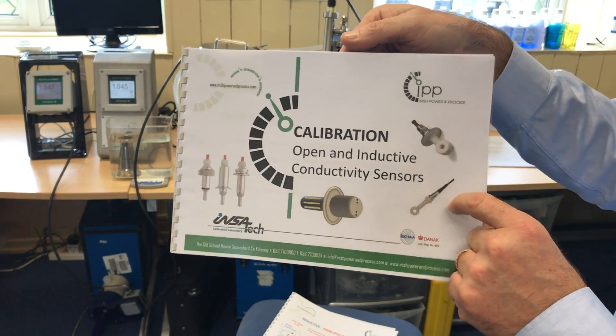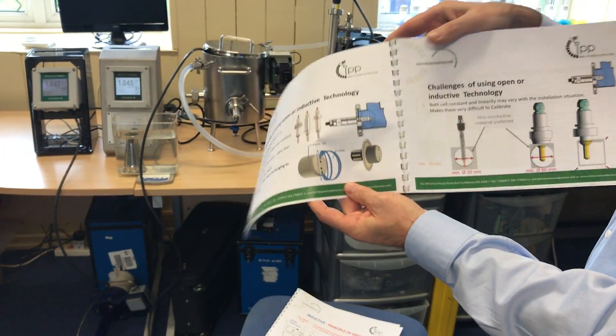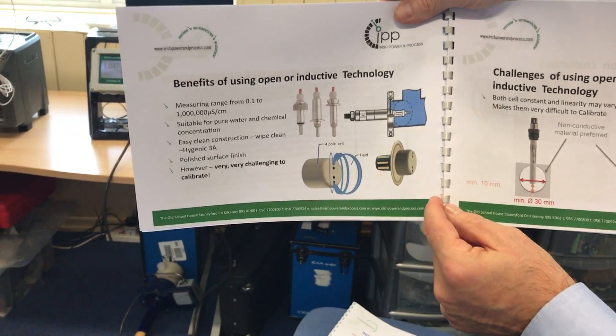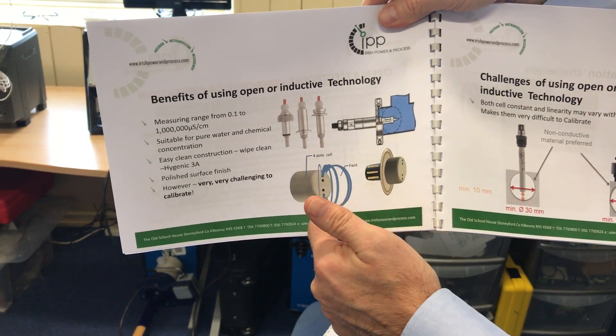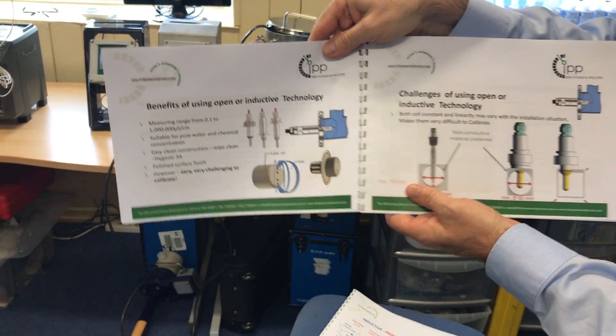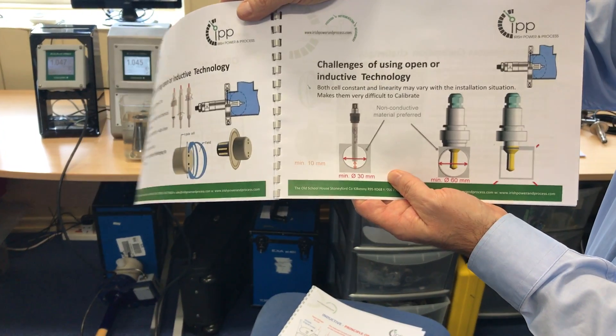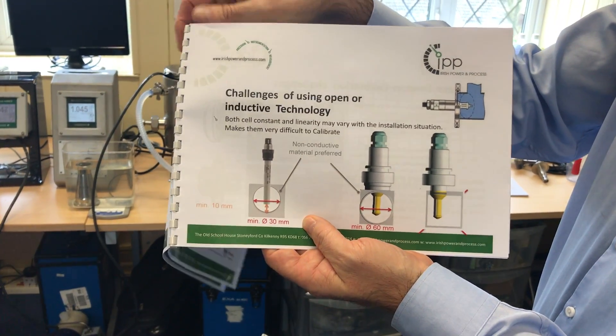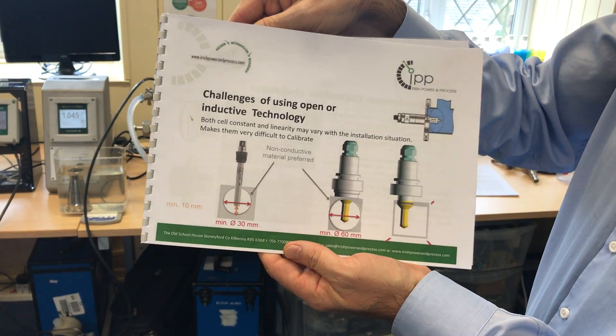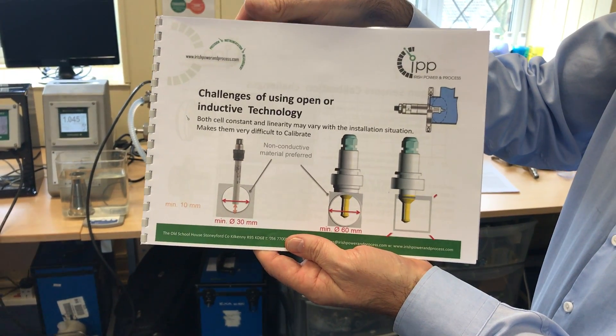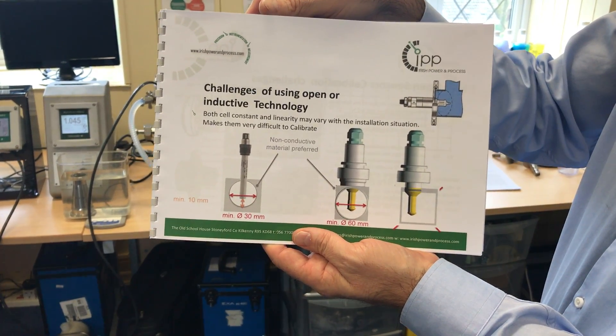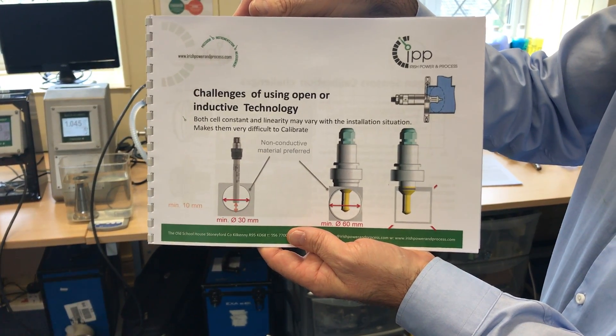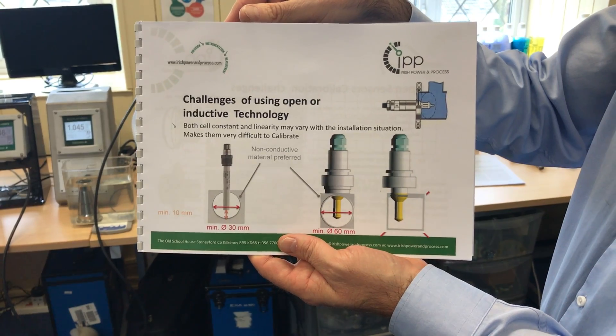These sensors are particularly influenced by their installation. They have an open field measurement, and how they're installed or orientated will have a huge influence — as much as 20% on the measurement. We hope to prove that now by showing you how we would use the Instacal conductivity calibrator to calibrate them correctly.